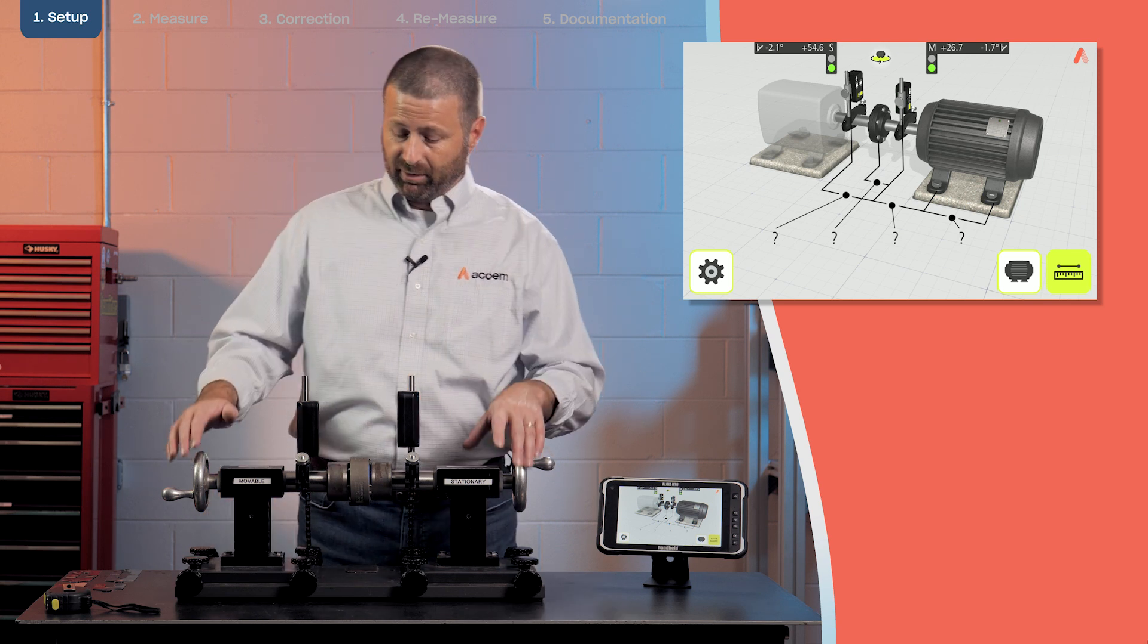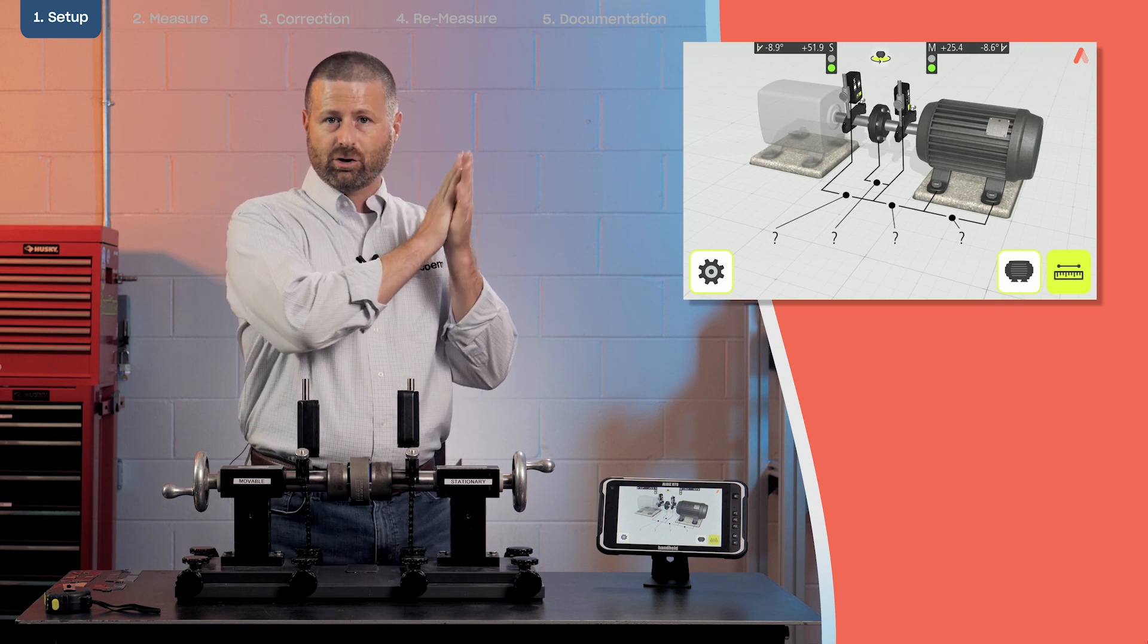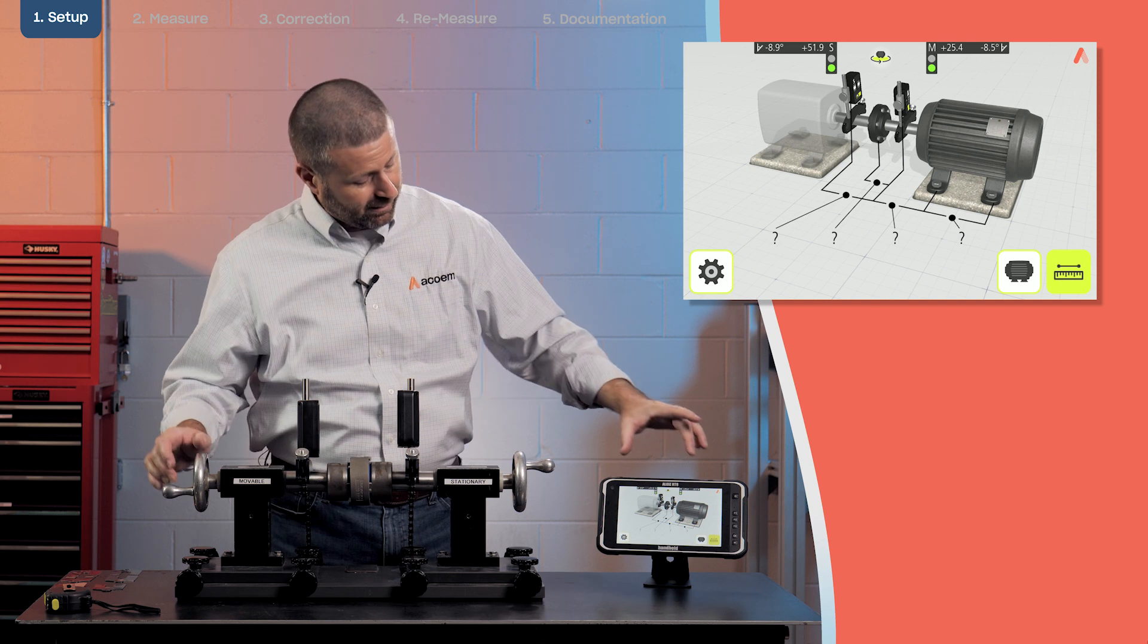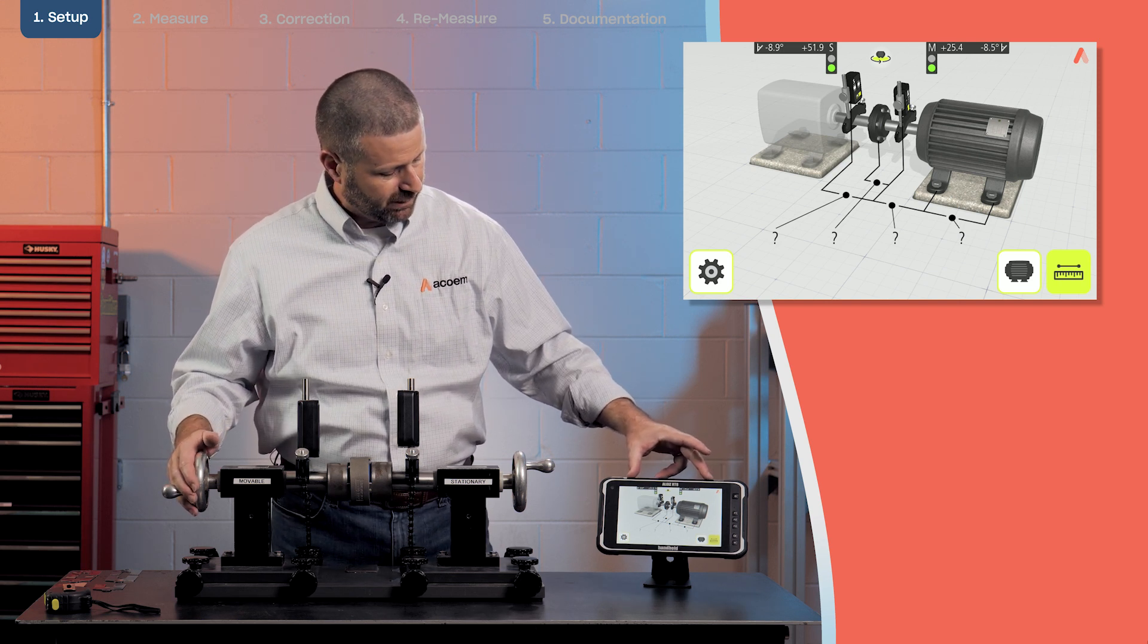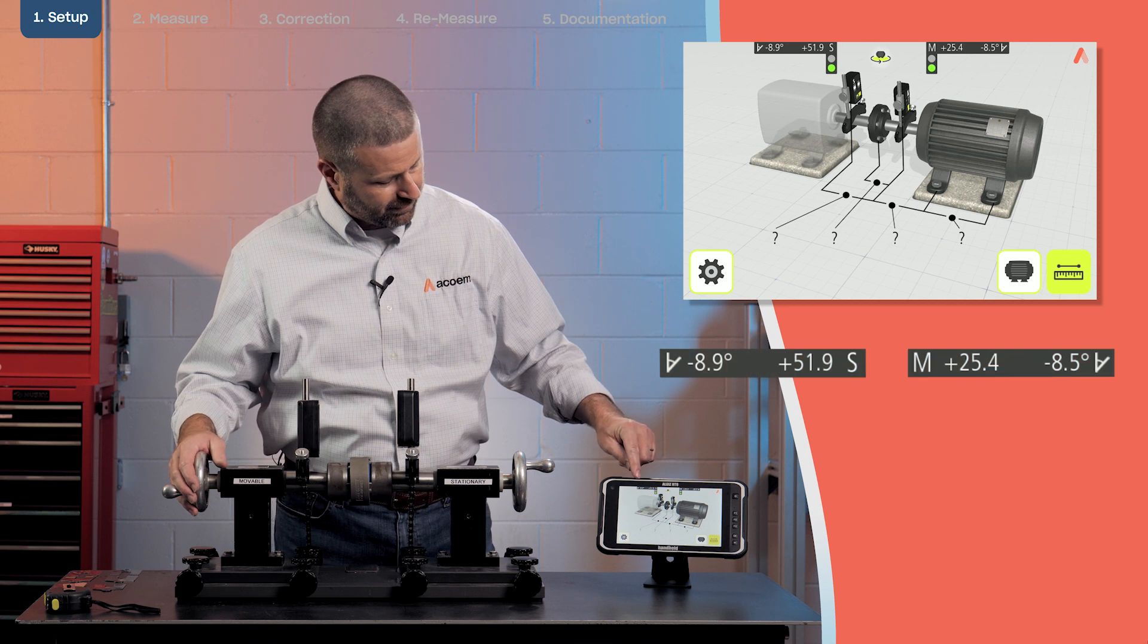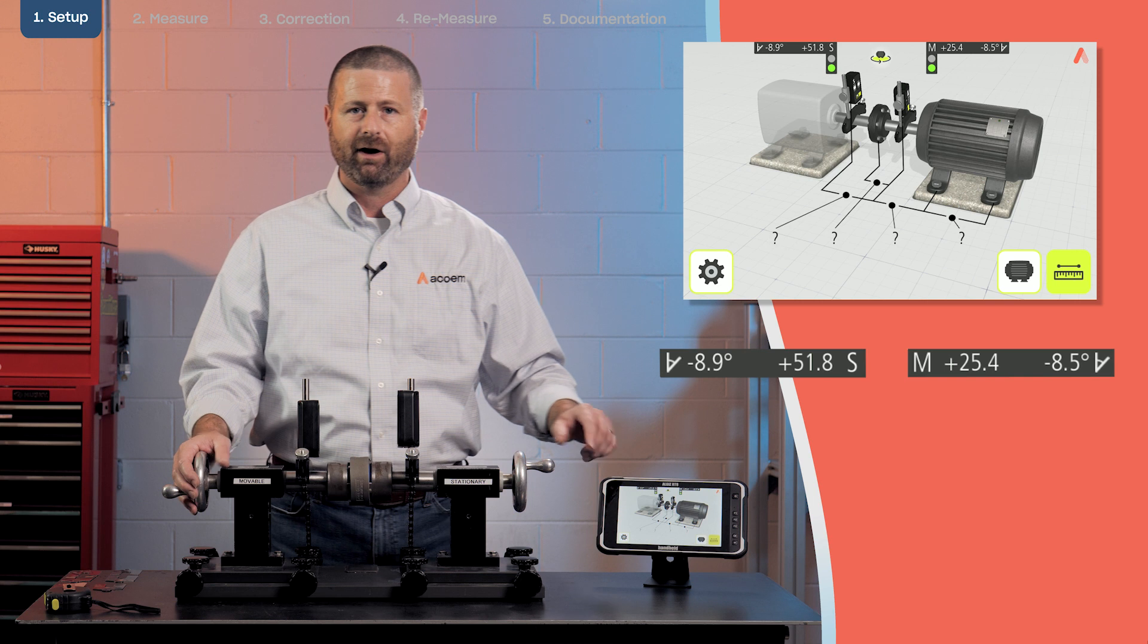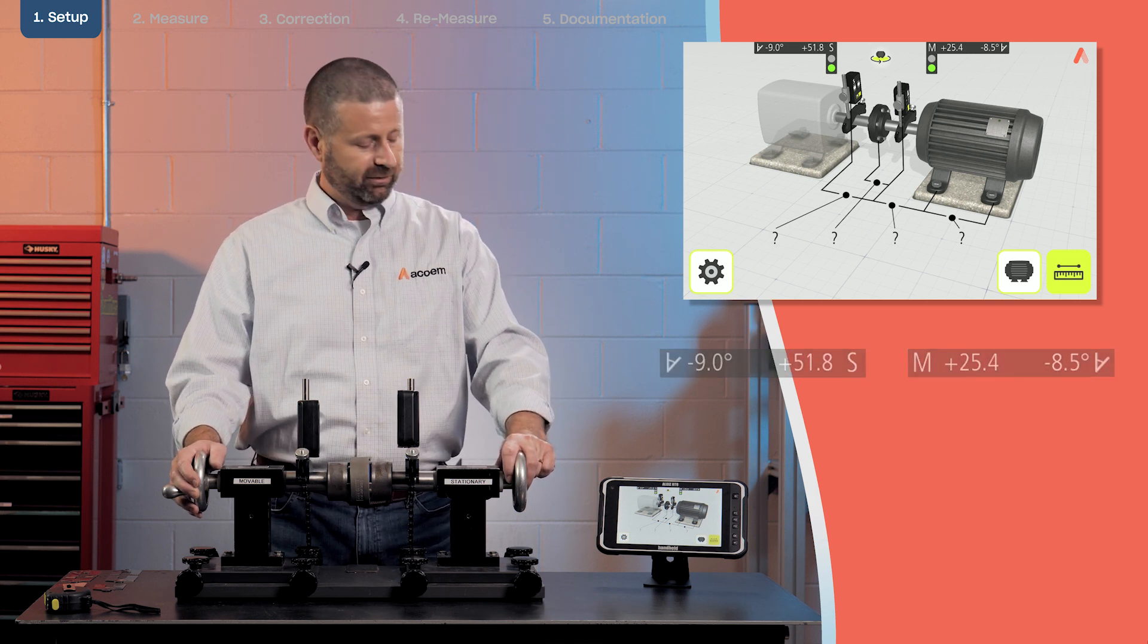The next step of course is also going to be that our sensors need to be square to one another. We can double check that by looking at the angle display on the display unit. In this case I have the S sensor at 8.9 and the M sensor at 8.5. These should be within about one degree of one another to start off with.